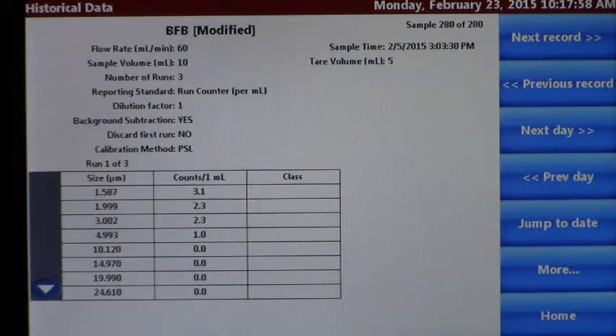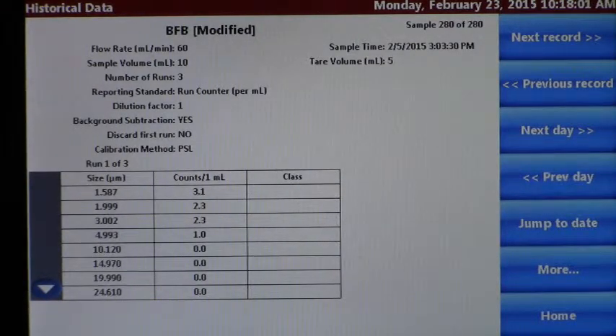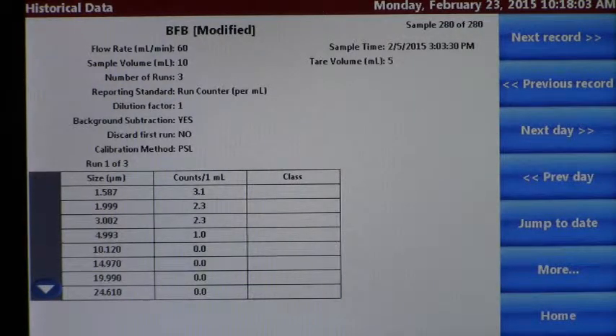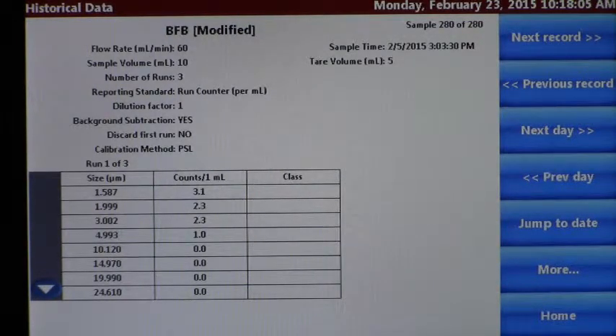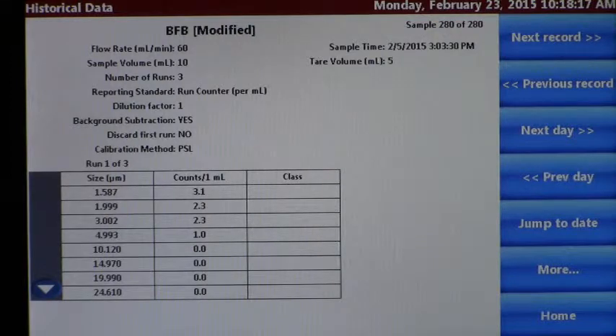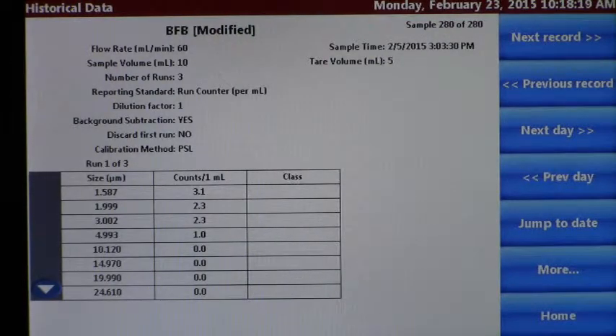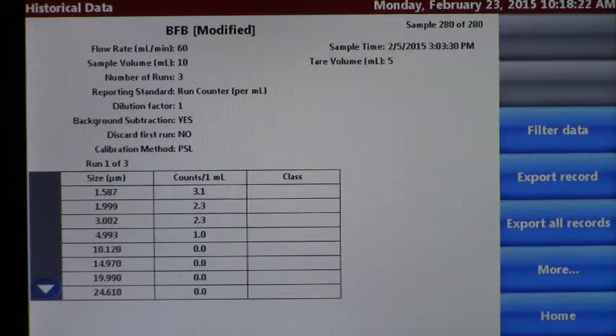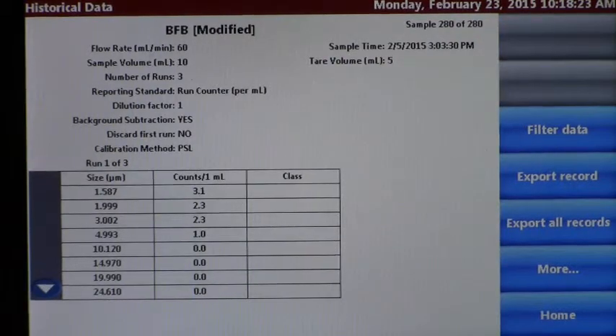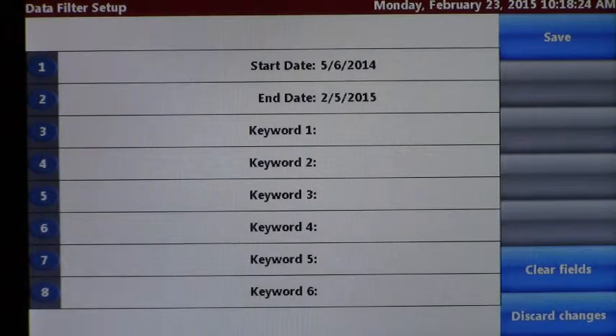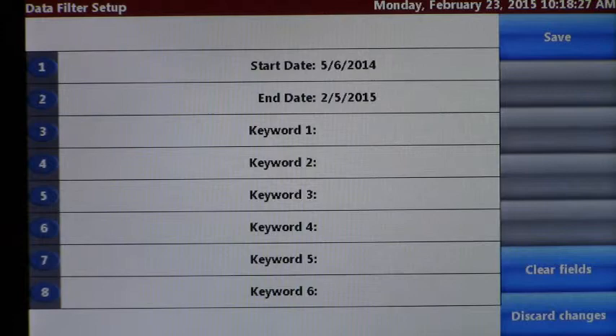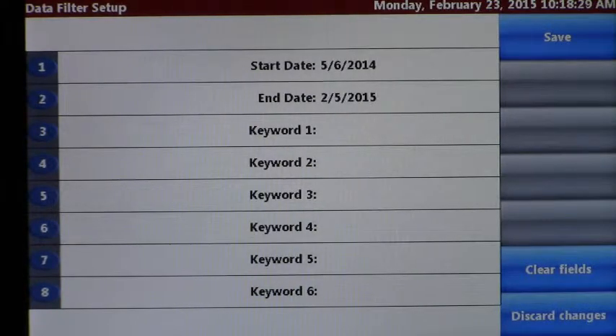At this point you can establish the data you want to be available at the web server or if you want to have all records set up for the web server. If you only want to provide a limited amount of data you would go to more, go to filter data, and you can set up your start date and the end date to what data you want presented on the web server.